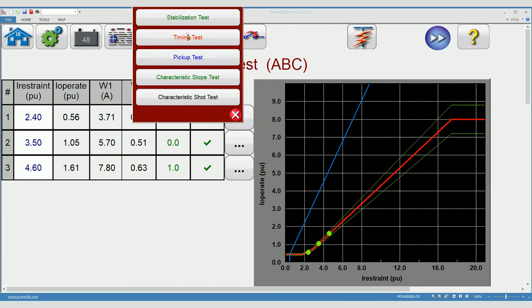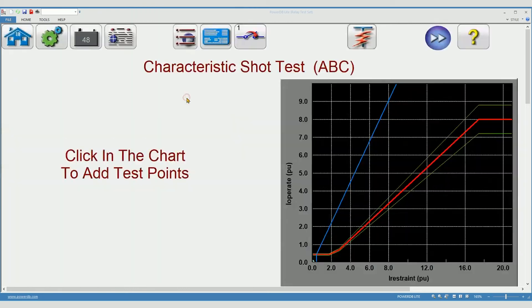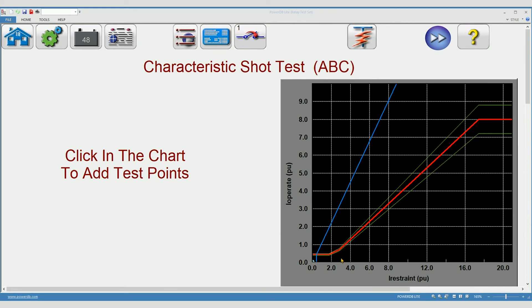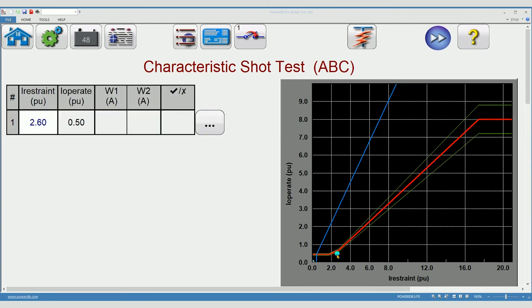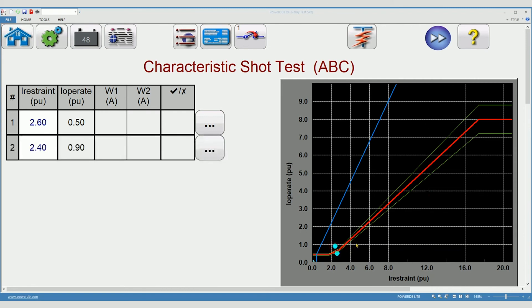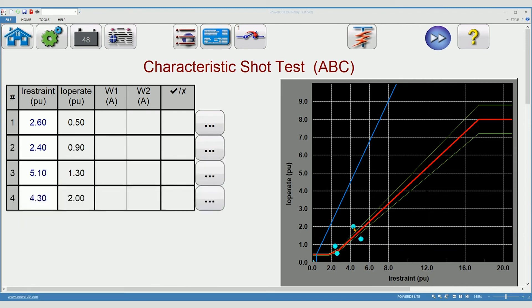The final test, not everyone runs this, is the characteristic shot test. The shot test is similar to the slope test, but instead of ramping and finding an operate point, it's a go or no go point. So you select the point you want to test, no op and op. We'll do one more, no op and op, and press the play button.